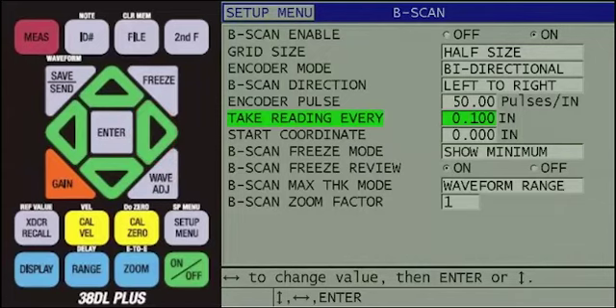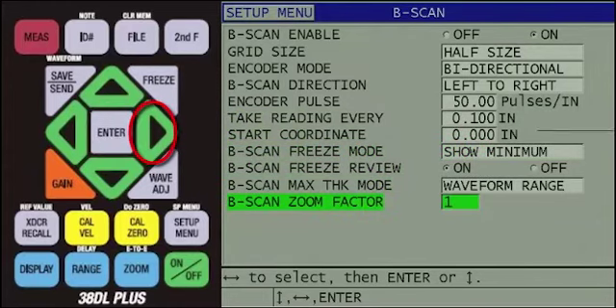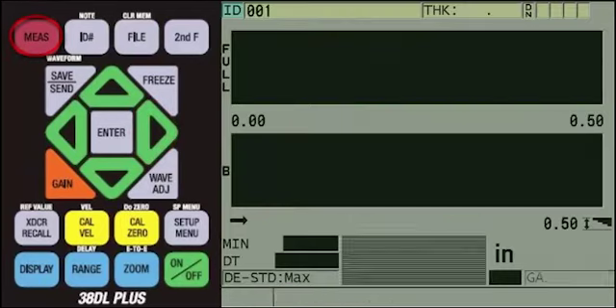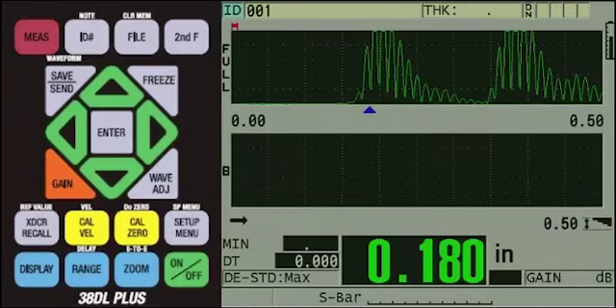This allows us to move the buggy at a more natural speed, while still having good scanning resolution while inspecting the sample. The only other setting we will change is the B-scan zoom factor. As discussed previously, an encoded scan with a zoom factor of 1 will yield a very compressed B-scan. To change this, keep pressing the Enter key until B-scan zoom factor is highlighted, then keep pressing the right arrow to change it to 8. You can then press the red Measure key to return to the measurement screen.